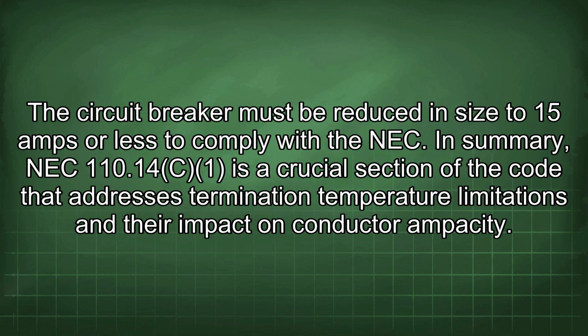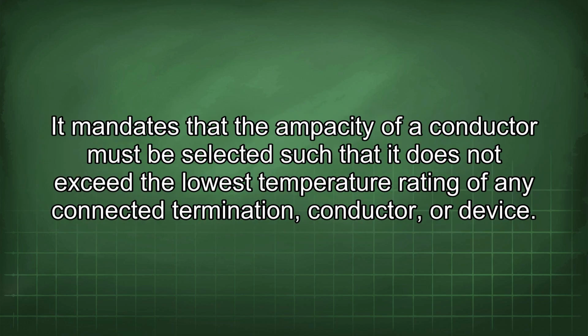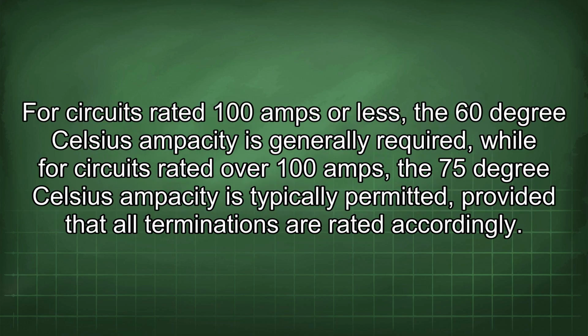In summary, NEC 110.14 is a crucial section of the code that addresses termination temperature limitations and their impact on conductor ampacity. It mandates that the ampacity of a conductor must be selected such that it does not exceed the lowest temperature rating of any connected termination or device. For circuits rated 100 amps or less, the 60 degrees Celsius ampacity is generally required, while for circuits rated over 100 amps, the 75 degrees Celsius ampacity is typically permitted, provided that all terminations are rated accordingly.